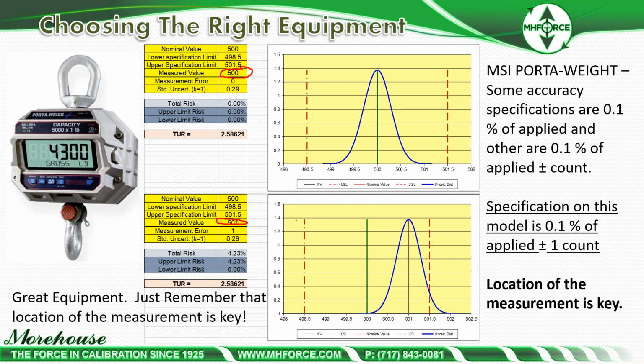Like I said, these instruments have very tight tolerance, and most of them come back in. The 20% that are typically out come out because of these first points where it's really tough. So here at 501, our total risk is 4.23%, which is too high. This is a situation where we're going to have to adjust it, and the end user's then going to have to make the determination if that risk was too high or not. It's just one of those things that's reported. They're tough to get in. When they do go out, that 20% that do go out, you get them back in. It's fine. The remainder of them are typically really good and hold their measurement.